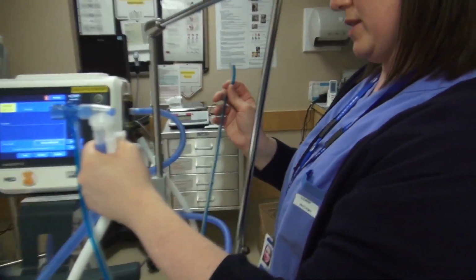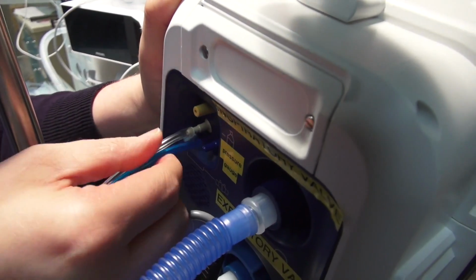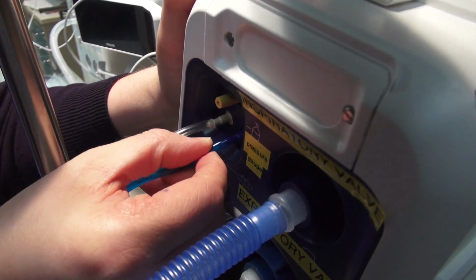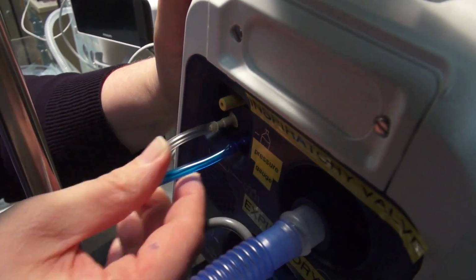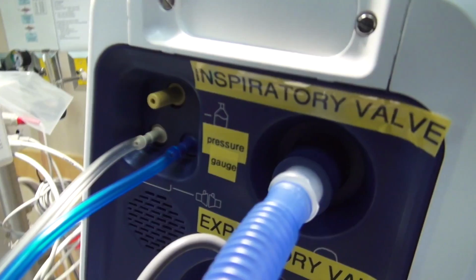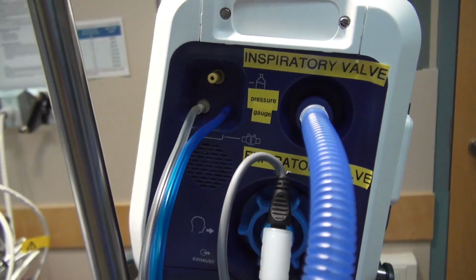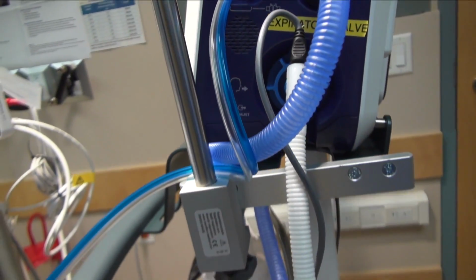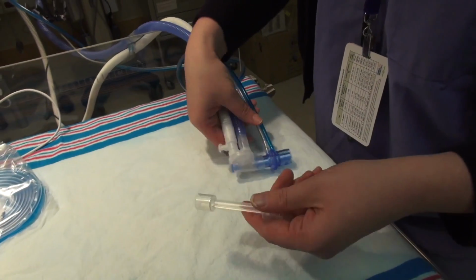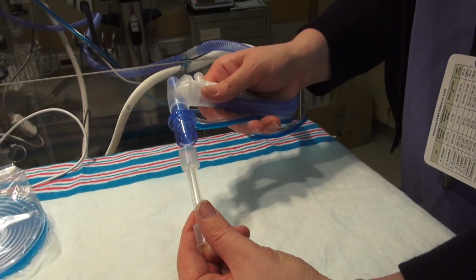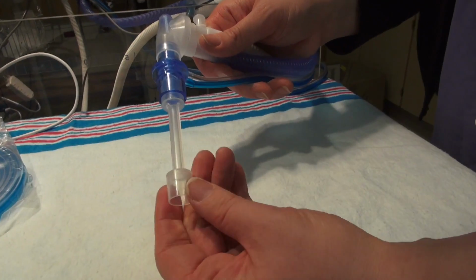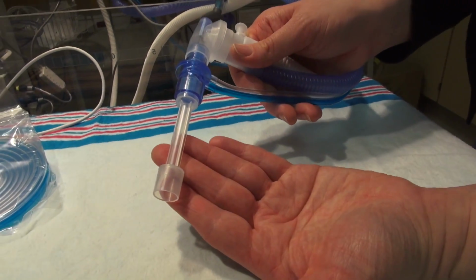Step 4. Attach pressure lines to ports on the side of the ventilator. Clear line attaches to the white port and the blue line attaches to the blue port. Step 5. Attach calibration adapter, used for the pre-op check only, to the end of the flow sensor circuit.